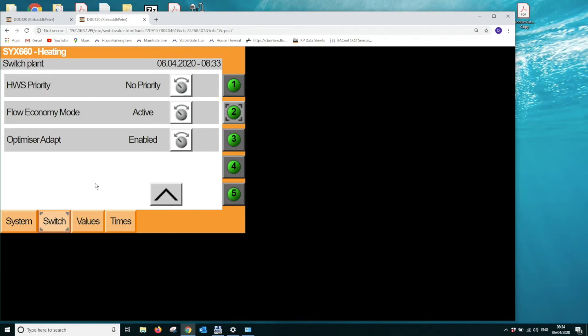Optimizer adaptation is the facility for the optimizer to learn the warming up rate and the cooling down rate of the building. There are some features in the controller where we'll touch on later about the optimizer warming up rate. If the building takes an extremely long time to warm up, then the warming up rate can become a very low number. If that number goes below 0.5, or effectively 0.5 degrees C per hour, that's a very long time. That would be 2 hours of heating for every degree C of heating for the building.